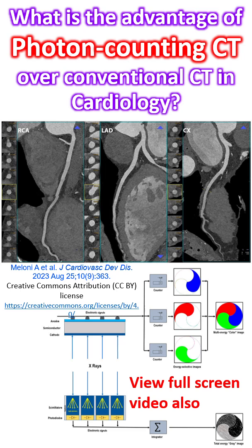The individual conventional CT detector cells are divided by optically opaque layers called septa. These are inactive areas of the detector surface causing loss of efficiency. Instead of the two-step conversion in conventional CT, photon counting CT uses direct conversion using a layer of semiconductor.